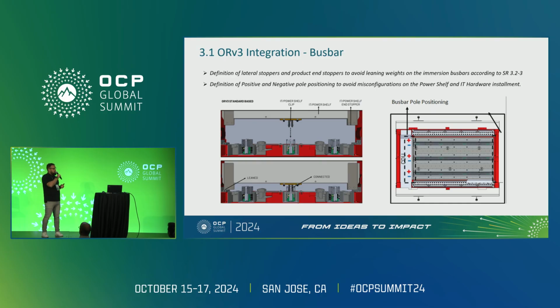If you're asking how the busbars are designed for immersion, they're actually mostly the same. We are going through a material compatibility review, since some of the OCP/ORv3 busbars use glue, so we're checking whether that glue can be diluted in immersion, or if there's any incompatible material. Besides that, it's just a matter of making the right size for our tanks, and we're good to go. There's nothing else we need to change or over-engineer. The busbars are completely fine in immersion, and as we said before, they can deliver much more density than in air.